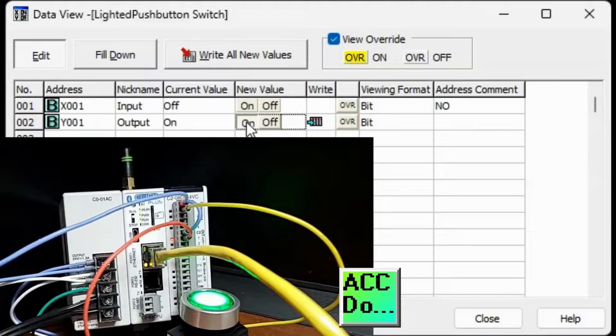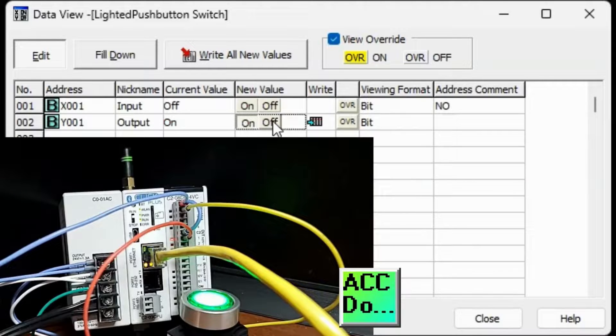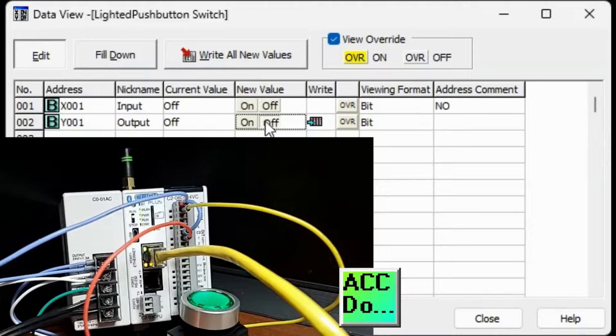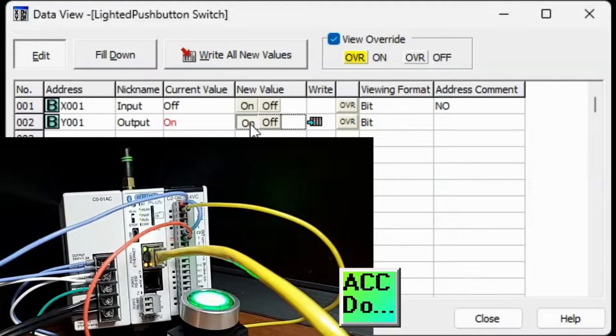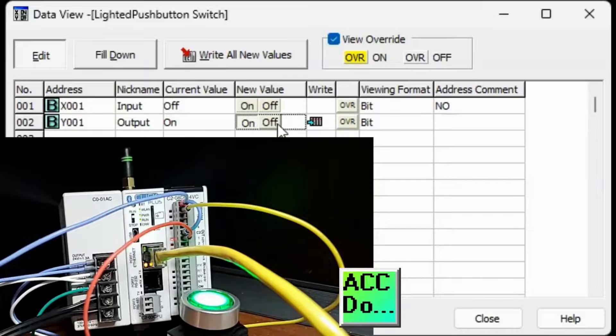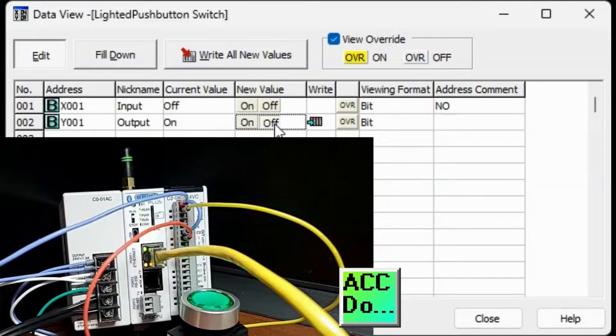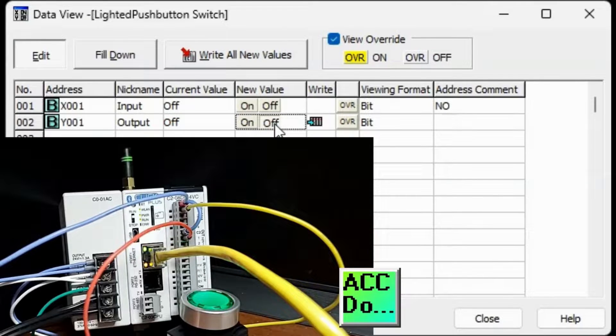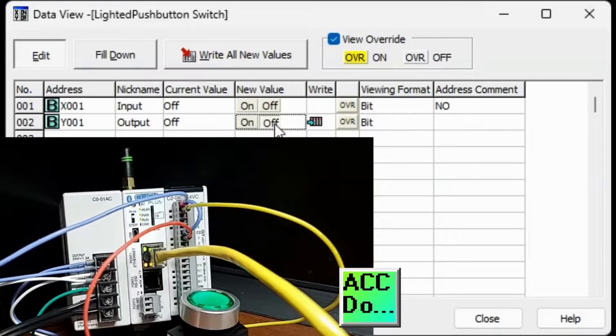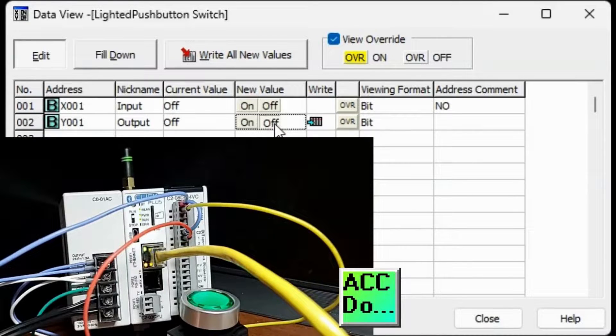Double clicking on the output will turn the physical relay output ON in the PLC. The pushbutton LED and the LED on the output I/O will be ON. Double click on the OFF to turn the output OFF. Ensuring that our inputs and outputs are working in the PLC is one of the steps in commissioning a PLC system.